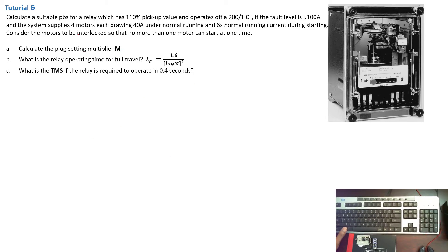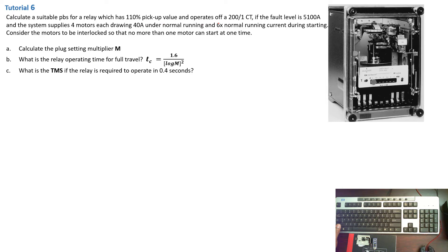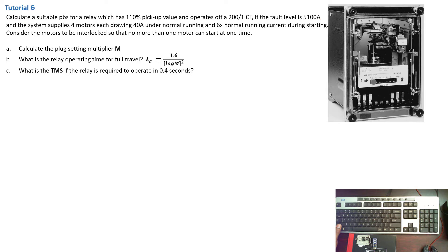This is tutorial number six on our series of tutorials on IDMT relays calculation. Now, in this tutorial, we are asked to calculate a suitable plug setting for a relay which has a 110% pickup value and operates of a 200 over 1 CT ratio if the fault level is 5100 amps.